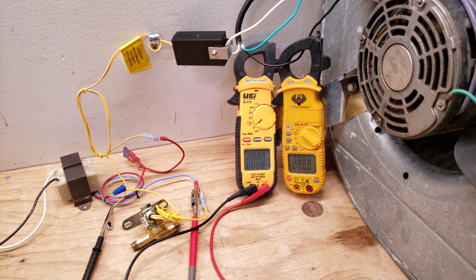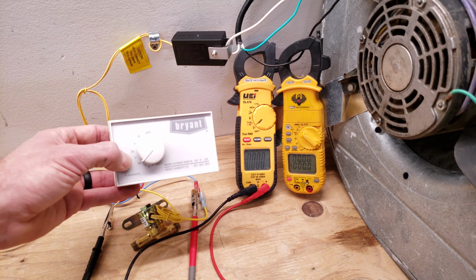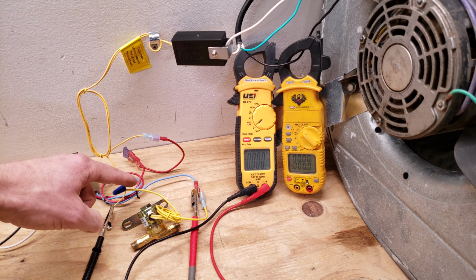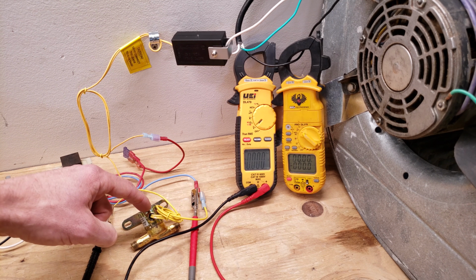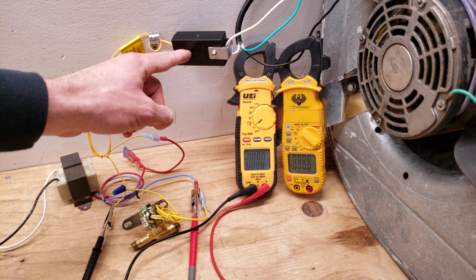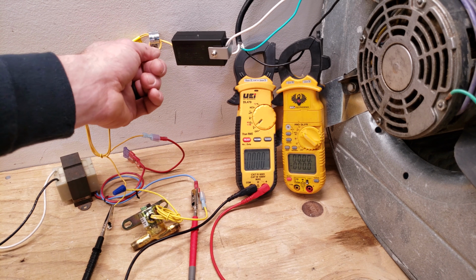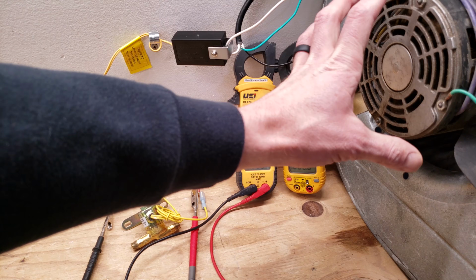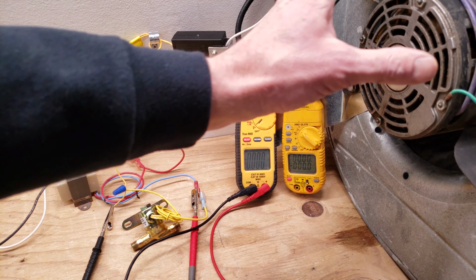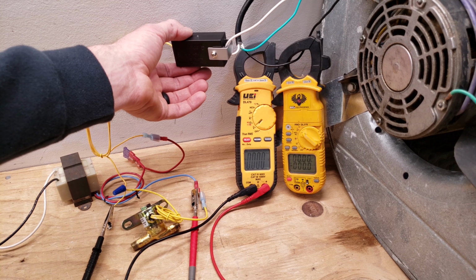Now typically in the field you're also going to have a humidistat that's going to break the power wire going over to the solenoid. And so this is only going to connect the wires inside if you have amperage being drawn by the blower motor. So the amperage has to be high enough. In this case, it has to be above 4 amps, at least that's what this is rated for.